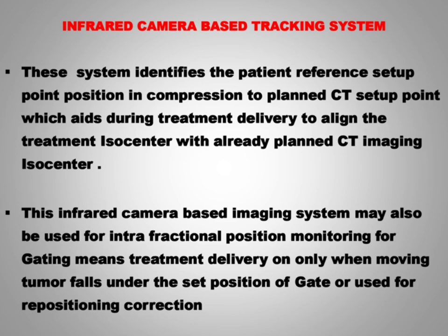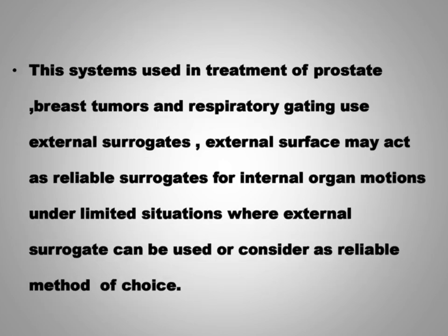The infrared camera based tracking system identifies the patient reference setup point in comparison to the planned CT setup point which we have already planned, and which aids during the treatment delivery to align the treatment isocenter with the already planned CT imaging system.